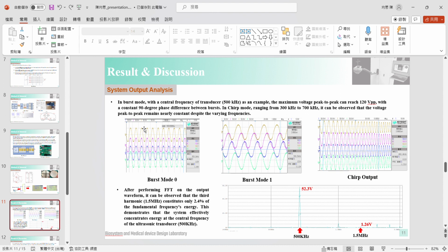And after performing a fast Fourier transform on the output waveform, it can be observed that the third harmonic, 1.5 MHz, constitutes only 2.4% of the fundamental frequency's energy. This demonstrates that the system effectively concentrates energy at the central frequency of the ultrasonic transducer.